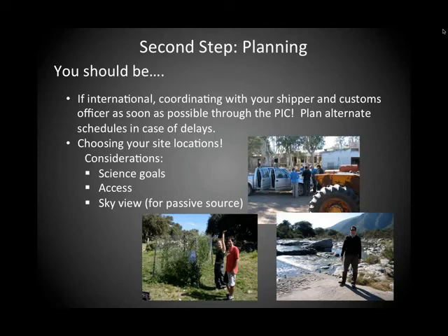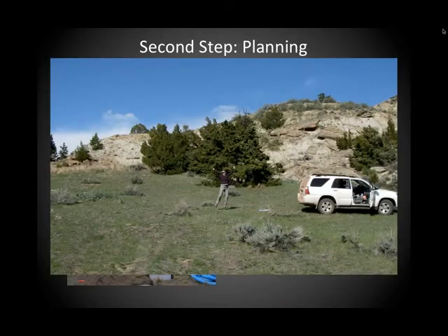They also provide many types of software, and in particular, field-ready log and data viewing software for reviewing state of health of your instruments, programming Texans, and also little computational tools for figuring out how much power you'll need for each site or for the total experiment, and how much memory you'll need for your data. And all of those tools are available through PIC and on their website.